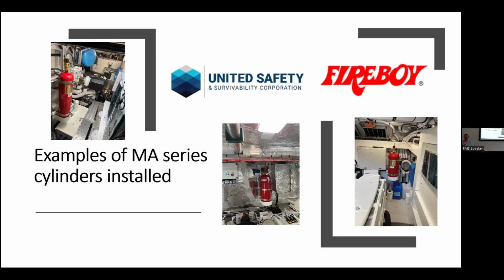Lots of the time we see nozzle positioned to the side, especially facing like the corner. That's not correct. You might want to ask them to face it in the room. You don't have to face the extinguisher towards the hazard. It's not like a dry powder or anything. So it'll flood the whole space when it discharges. So it doesn't have to be close to the engines.